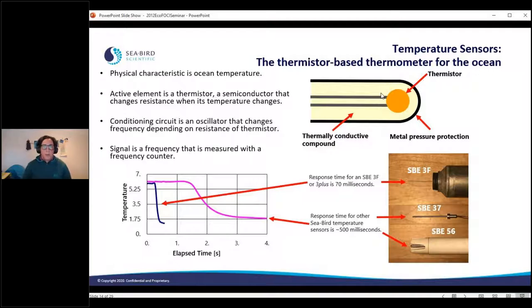Also in the design process, you want to make sure the thermistor itself is the same temperature as the actual water you're measuring. So the thermistor is inside this metal sheath, but it also has a thermally conductive compound to ensure the temperature matches.